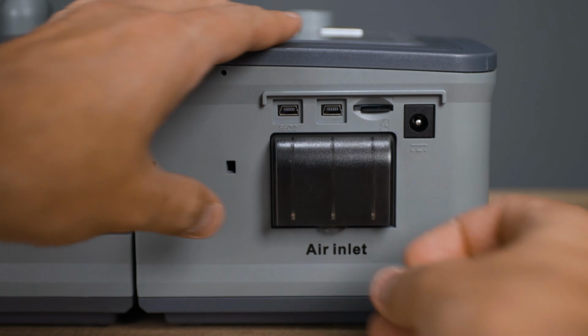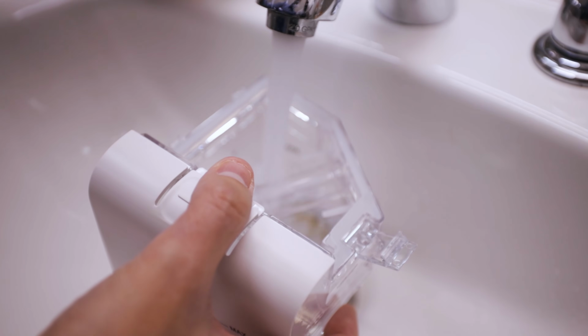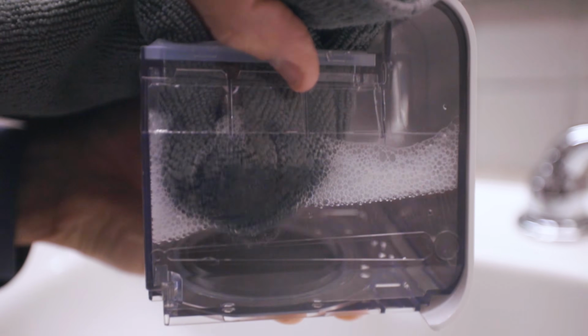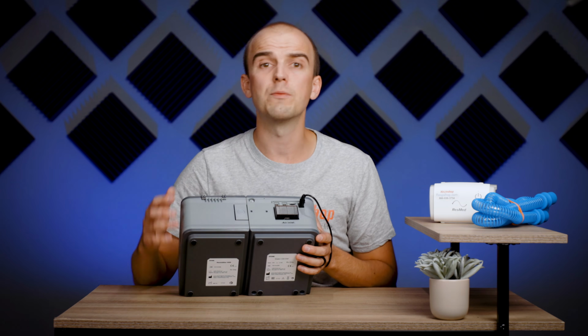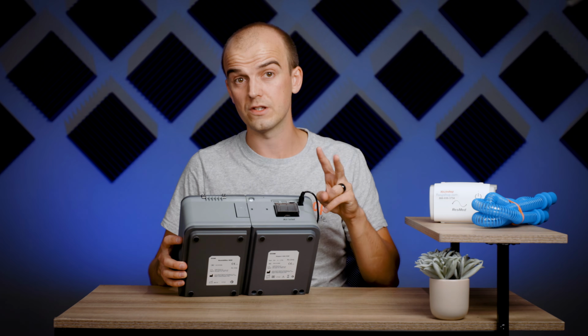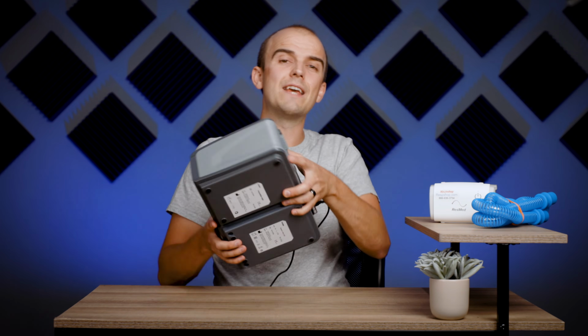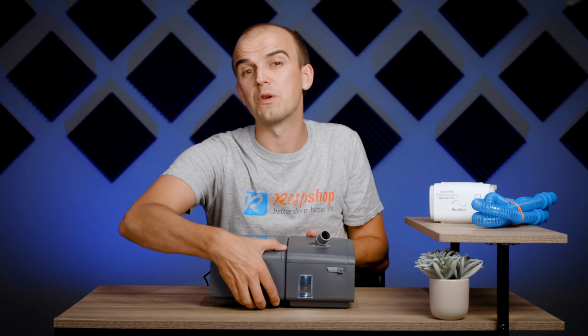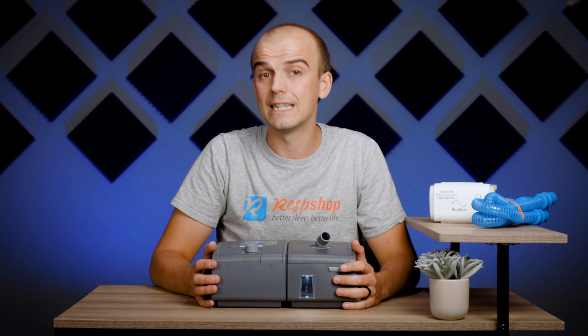Wash the filter in the same way that you do for the humidifier and tubing, with warm, soapy water, and then air dry. The machine ships with 2 filters, and they should be replaced at a minimum of every 6 months. But if you live in a dusty environment or in a home with pets, it's quite likely that you'll want to replace them more regularly than that.